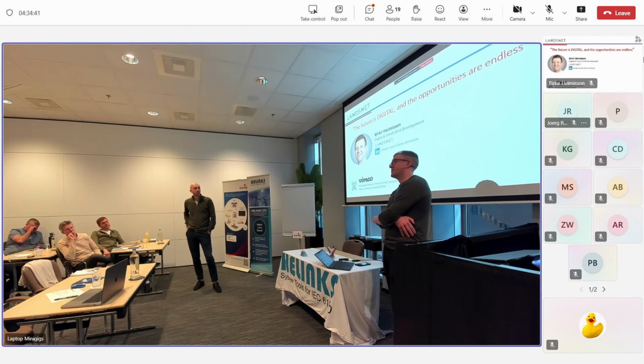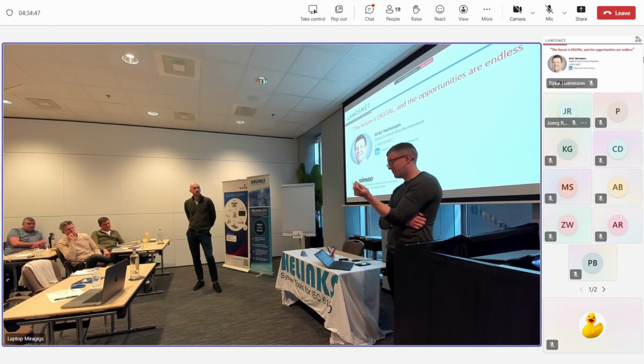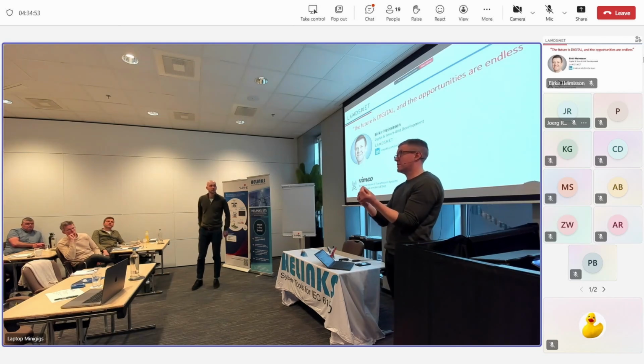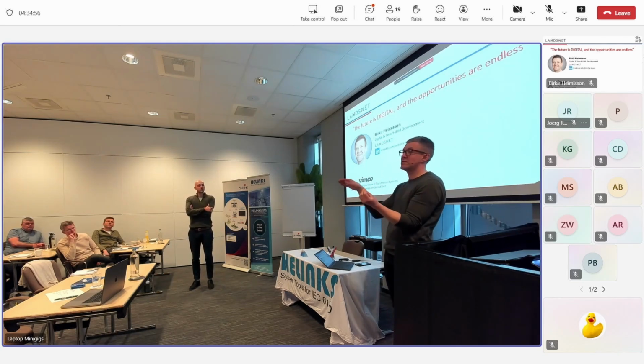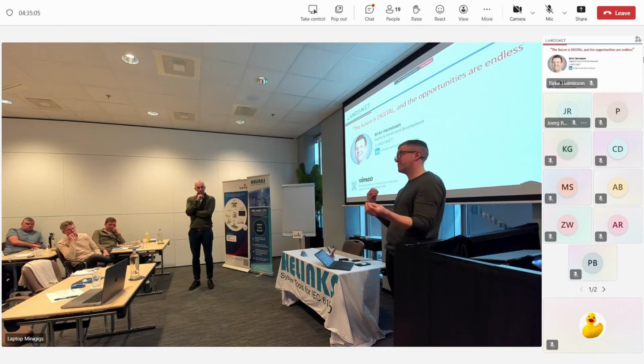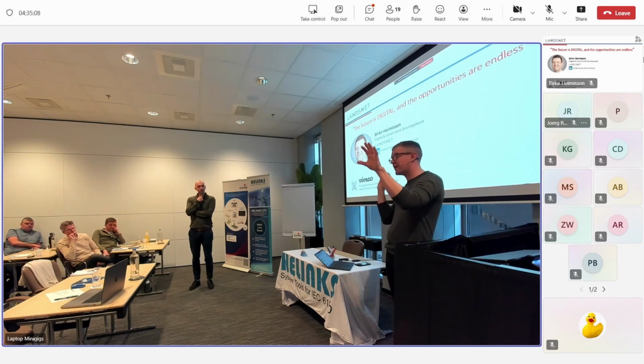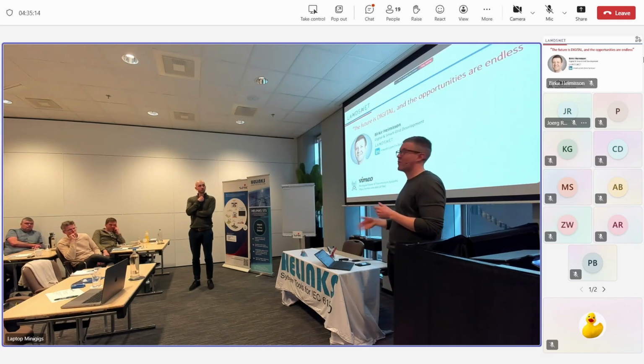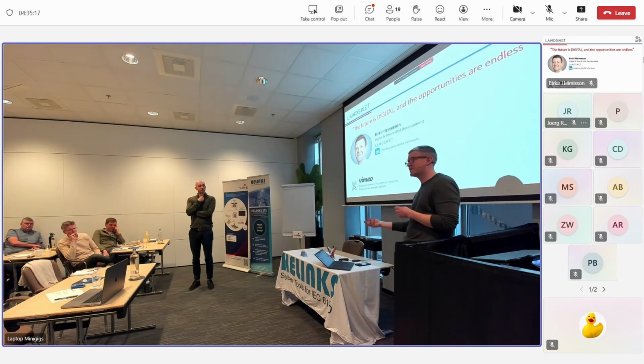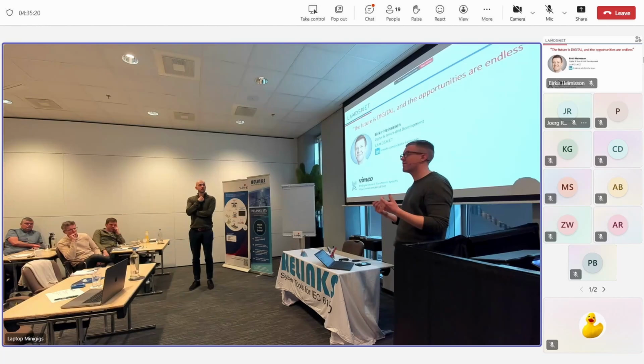On a recent project we saw the client wasn't getting reports, it was just polling the data. To get access to a report we tried removing the reservation — took it out from the SCD file for that connection, put it back in, and then it worked. So there was some kind of functionality issue between different versions of our HMI and the IED we had at the time, which was breaking things. That's what we've built into our test process now: making sure everything is properly subscribed and testing whether your reservation is working.